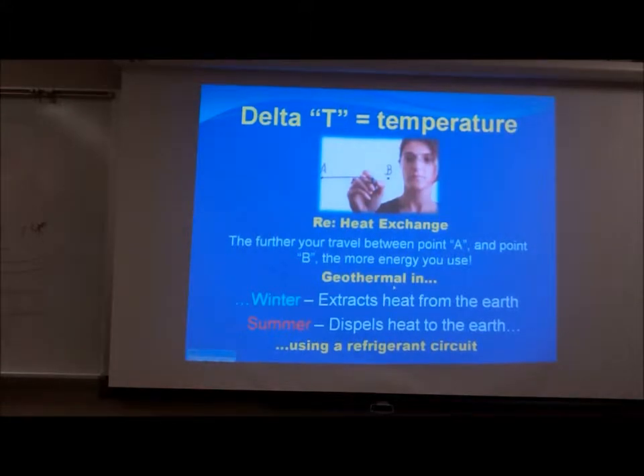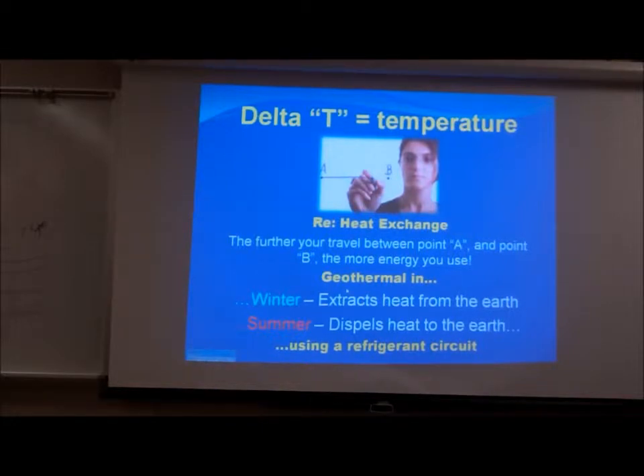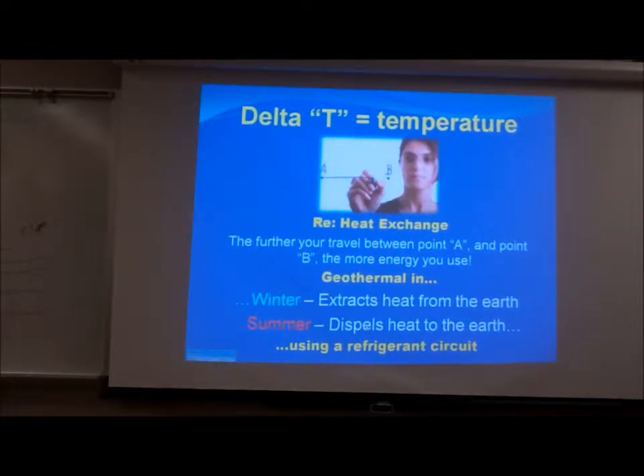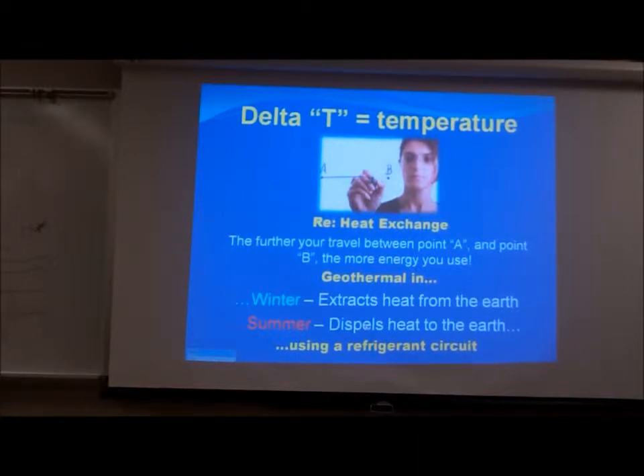Again, delta T. In the winter I'm extracting stored heat — solar gain. The geothermal heat pump is really nothing more than a solar energy management device. So I'm extracting heat from the earth in the winter, and I'm dispelling unwanted gain to the earth in the summer. The further I travel between point A and point B, the more energy I use. It's that simple.